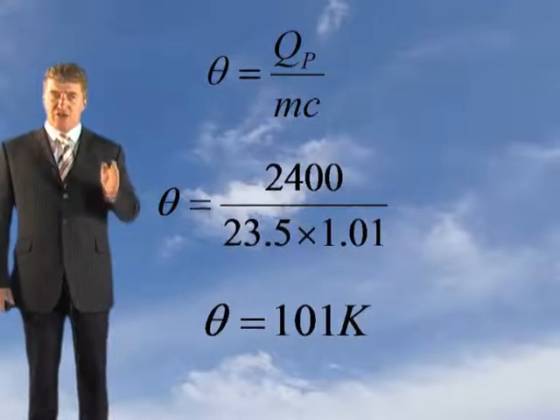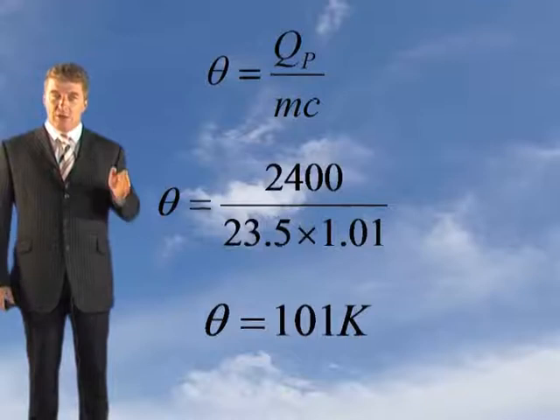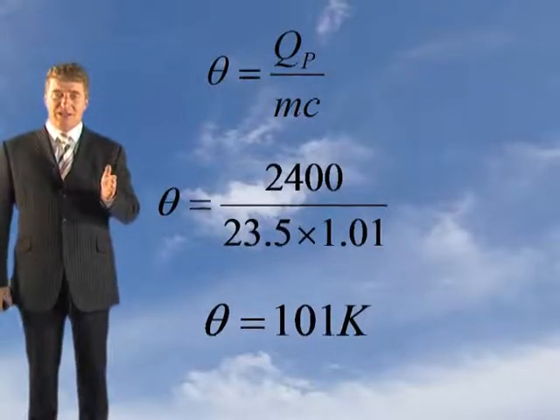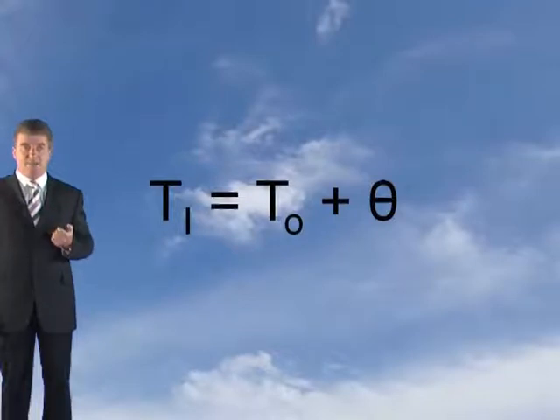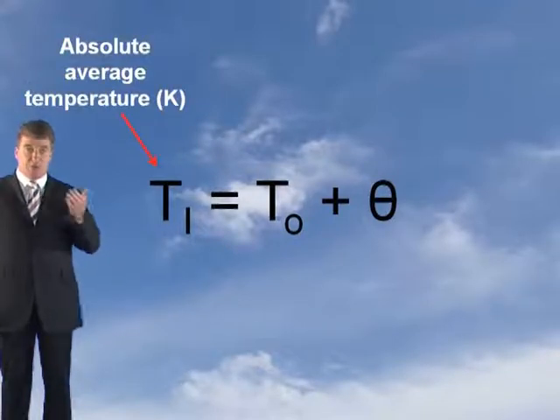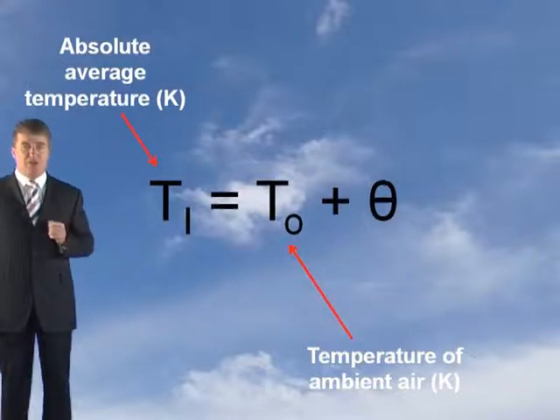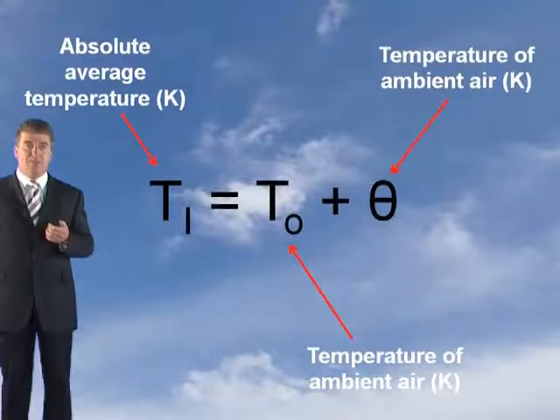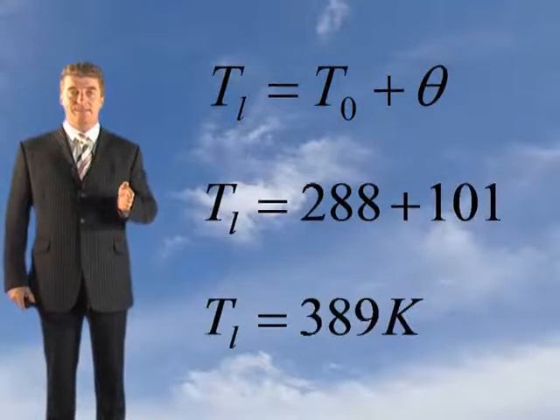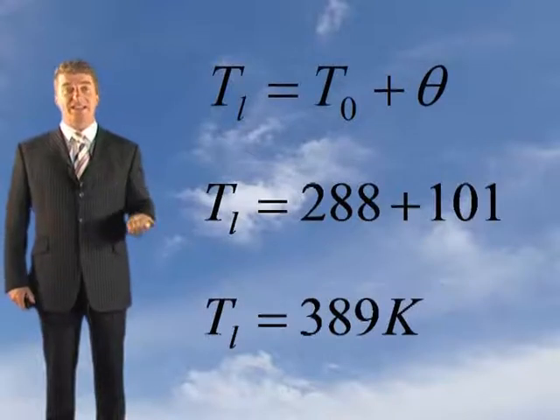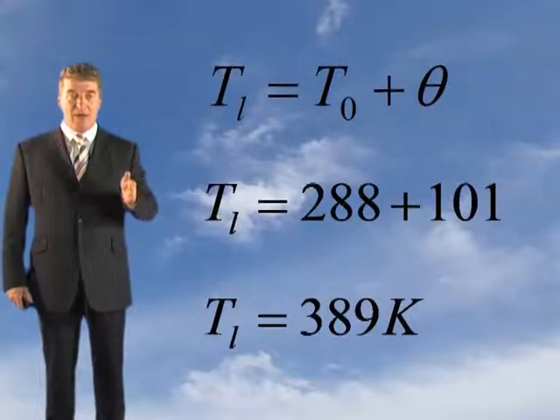101K — this is hot enough to ensure that the smoke has sufficient buoyancy, but not too hot for the life safety requirements. 200 degrees C is the critical temperature for life safety. We know the temperature increase, but how hot is the smoke? You use: TL equals TO plus theta, where TL is your absolute average temperature, TO is the ambient temperature generally taken as 288K, and theta is your temperature increase. Evaluating it gives a smoke temperature of 389K. And since 200 degrees C is the tenability limit, this is way below that — this is tenable. That covers step four.